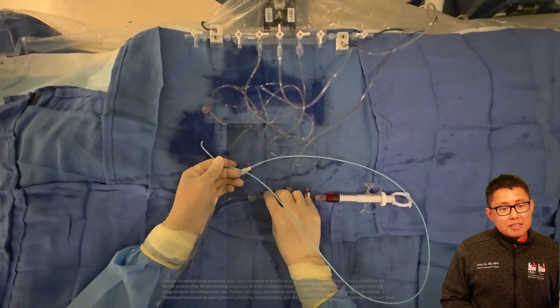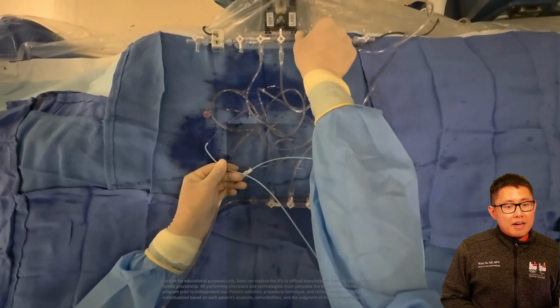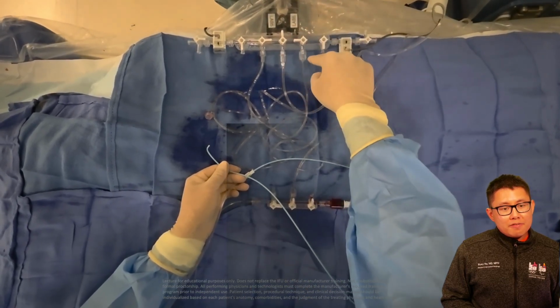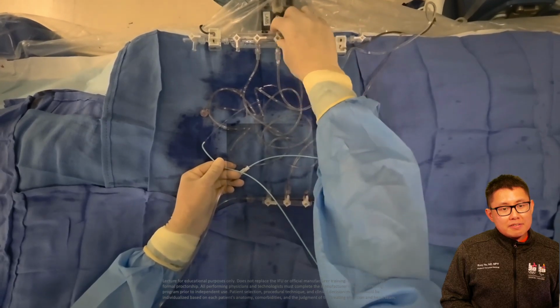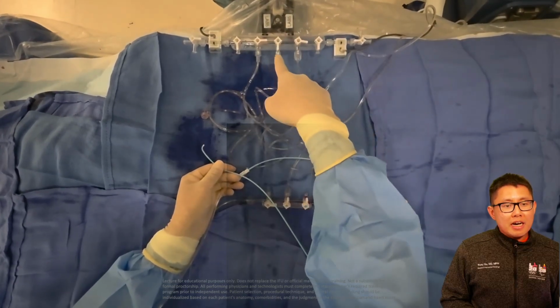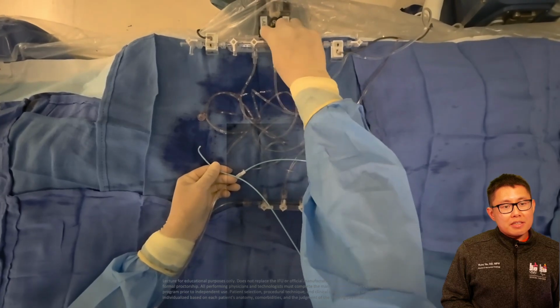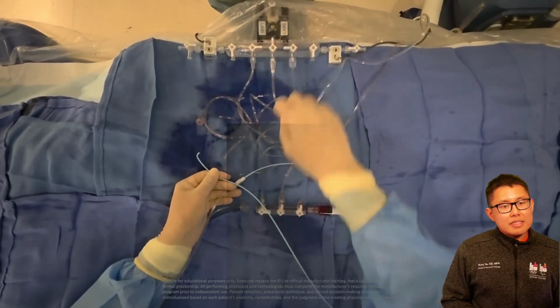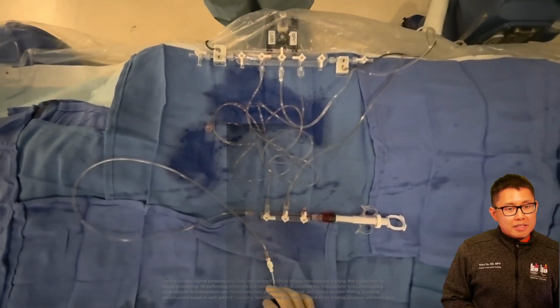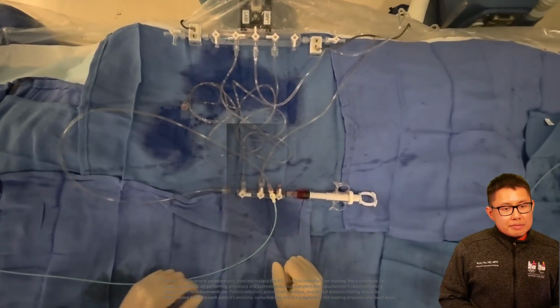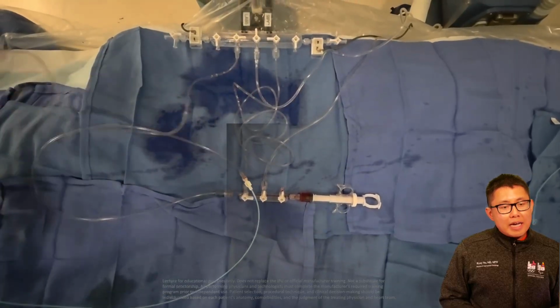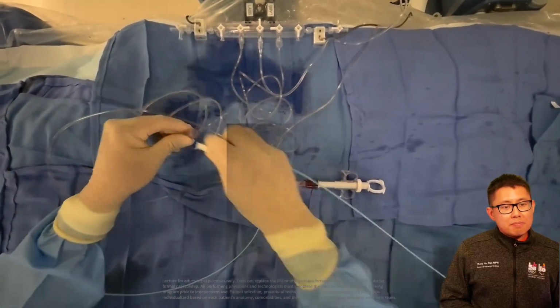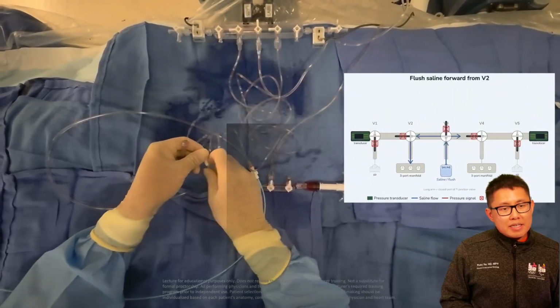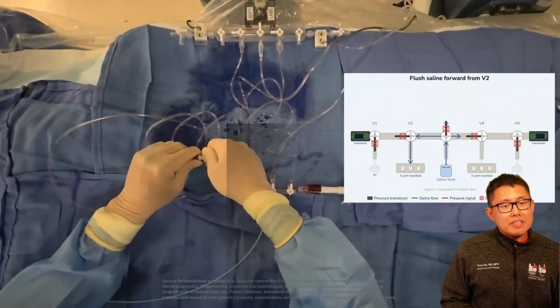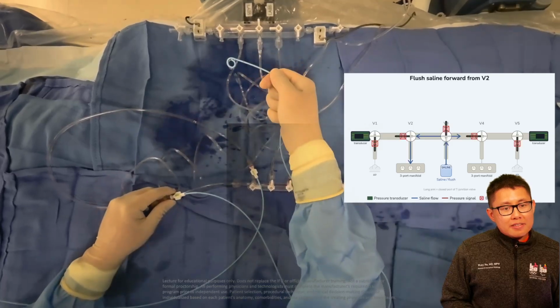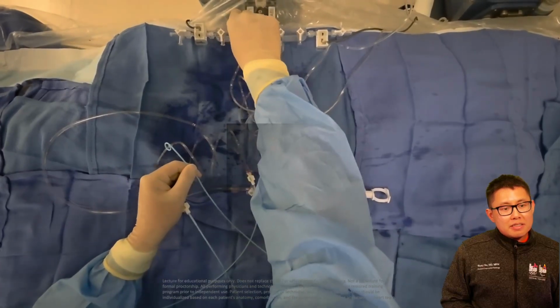There are actually several ways to turn off that flush. You can turn it off at the 3-port manifold or the 5-port manifold at V1 or V4 respectively, or you can turn off the source itself by turning off the saline pressure bag at V3 with the long knob down. But let's turn the long knob up because we need to do other business. There are many situations when you need to have a second catheter connected, and you would plug this into V2. So let's have our saline flowing forward by having V2 pointing to the left. So the saline flows from V3 down to V2, down to this pigtail catheter.